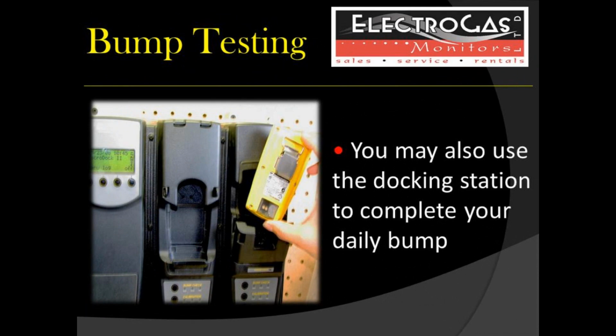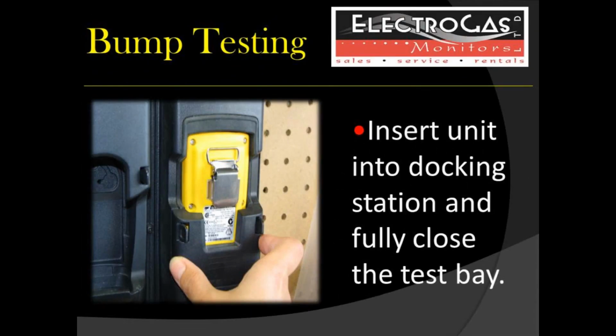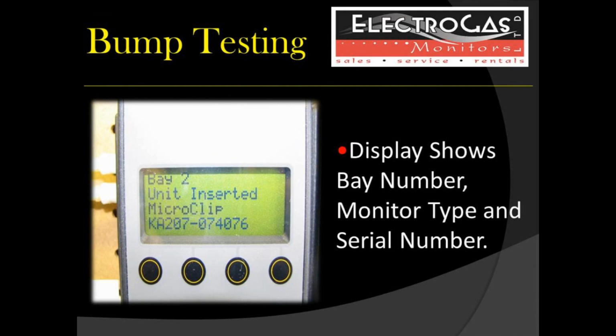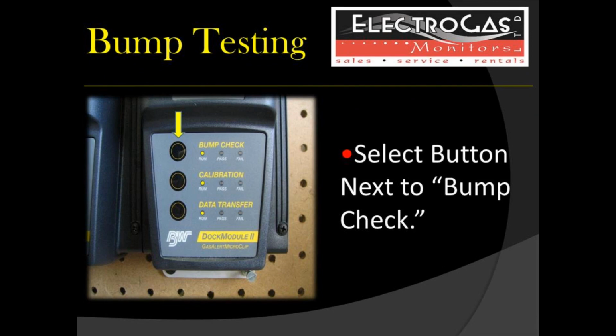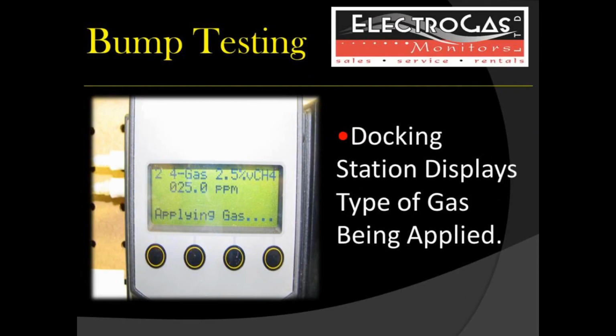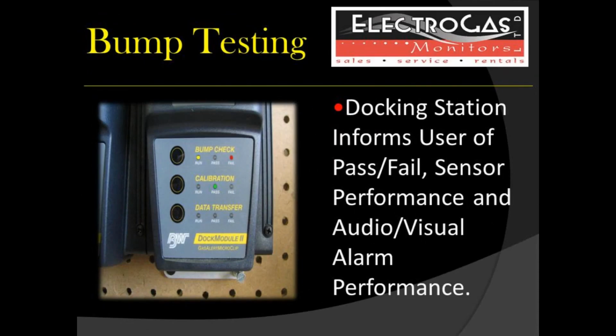As stated earlier, you may also use your BW MicroDock 2 system to complete your daily bump test. Insert the unit into the station face down and fully close the test bay. The display on your docking station will show bay number, monitor type, and serial number. Press the button next to Bump Check on your test module. Your docking station will now display the type of gas being applied. The docking station will show you whether your monitor passes or fails, while the display shows sensor performance as well as audio-visual alarm performance.